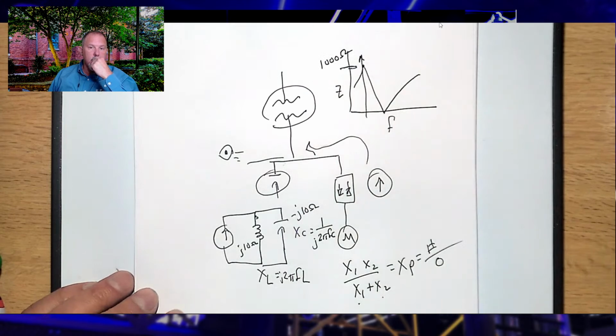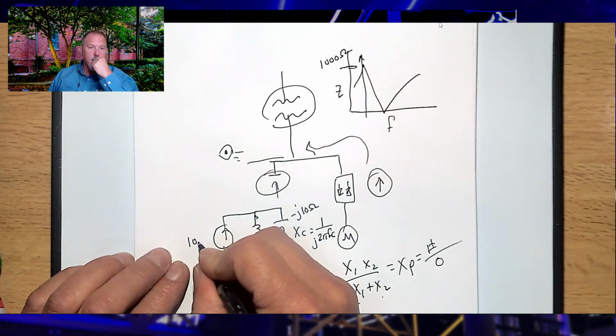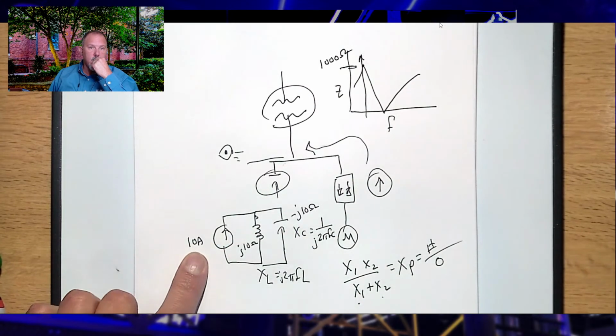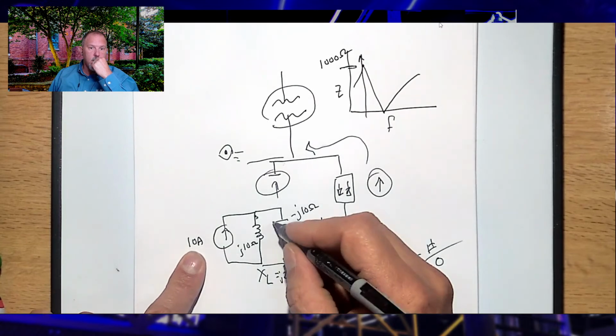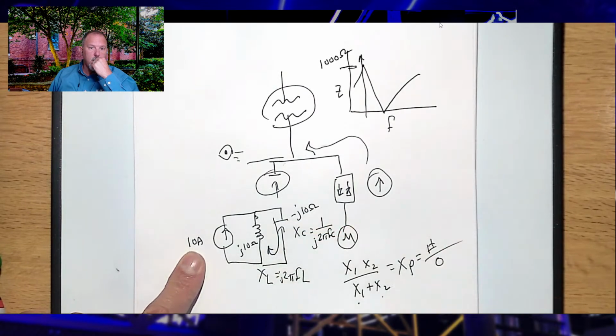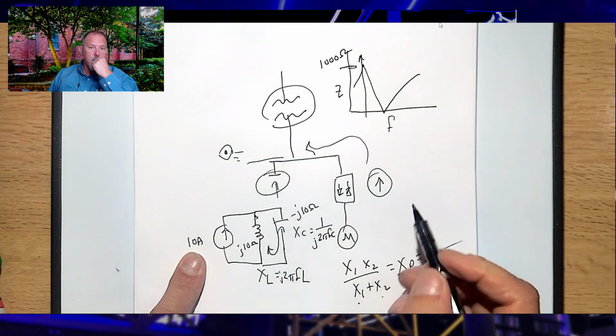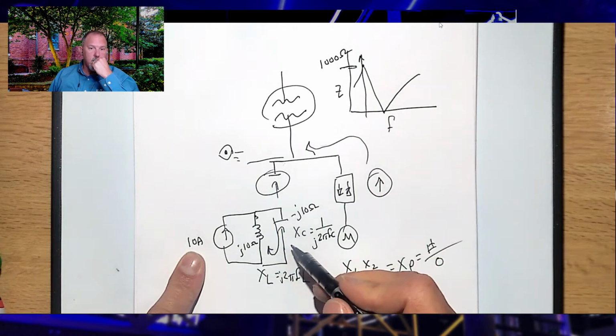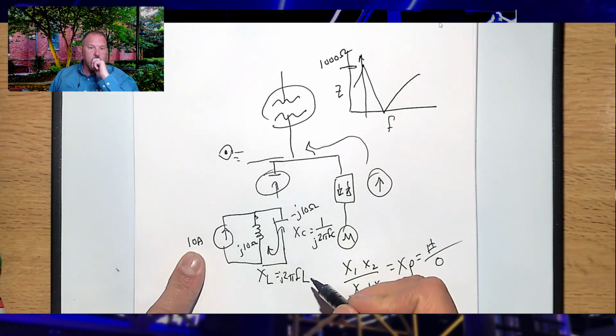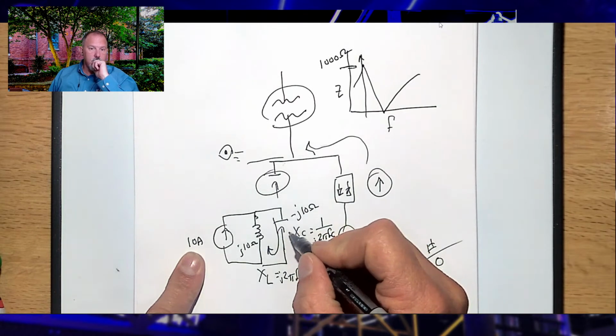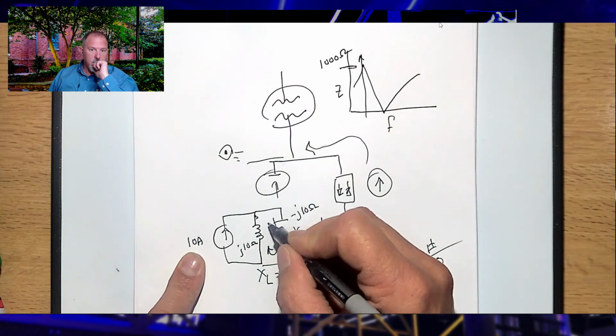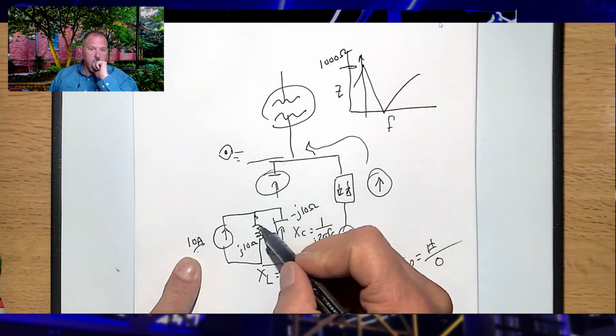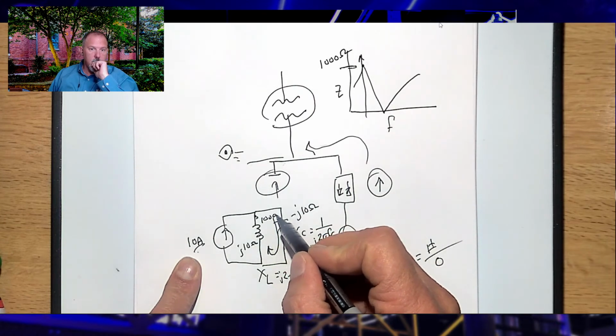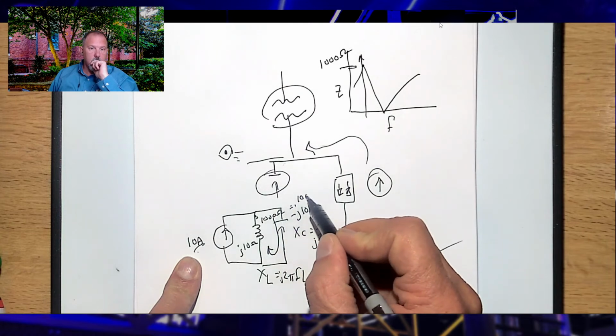So I put out 10 amps of harmonic current here. What's going to happen in this circuit, the tank circuit, the resonance circuit between these two? At some frequency I'm going to hit resonance, and this current is going to flow in this loop. Let's say it's 1,000 ohms. Well, if it's 1,000 ohms, that means I've got 10 amps times 1,000 ohms equals 10,000 volts.